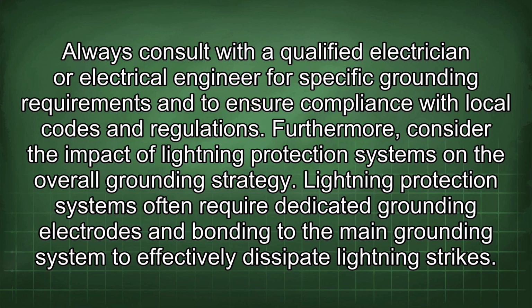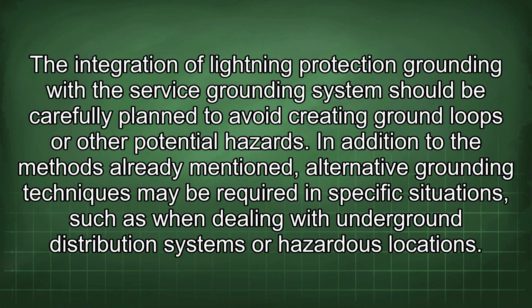Furthermore, consider the impact of lightning protection systems on the overall grounding strategy. Lightning protection systems often require dedicated grounding electrodes and bonding to the main grounding system to effectively dissipate lightning strikes. The integration of lightning protection grounding with the service grounding system should be carefully planned to avoid creating ground loops or other potential hazards. In addition to the methods already mentioned, alternative grounding techniques may be required in specific situations, such as when dealing with underground distribution systems or hazardous locations.